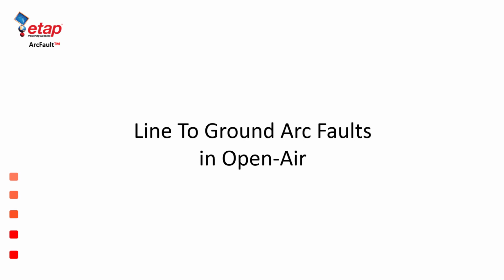Now, let's focus our attention on the most common and most important type of arc fault model. The line to ground arc fault, as I mentioned previously, was the choice test condition to develop the equations used by ETAP ArcFault Method 2. And it is currently the arc fault or arc flash mode of failure that is required for analysis by OSHA and is commonly mentioned in the National Electrical Safety Code standards.